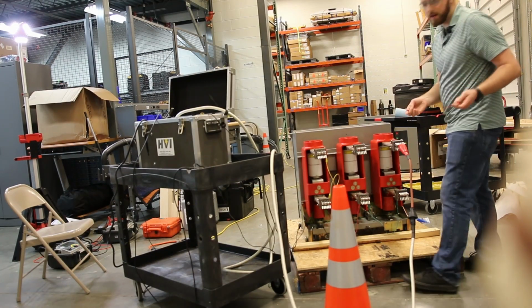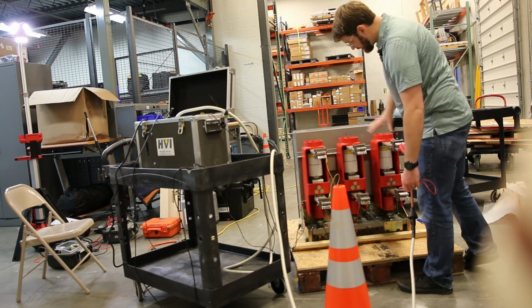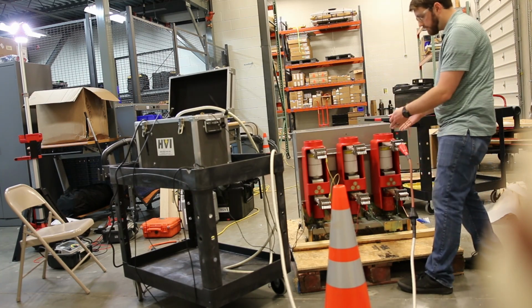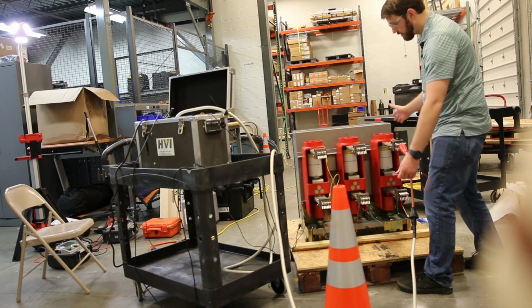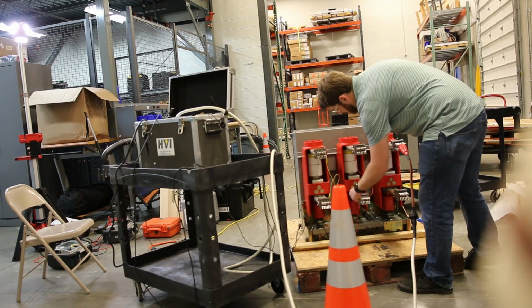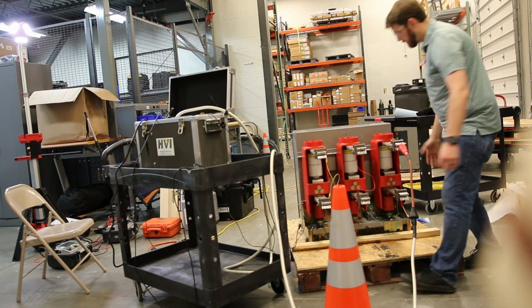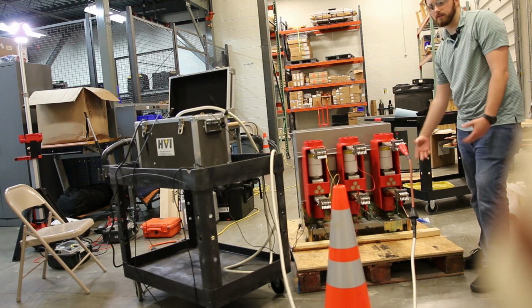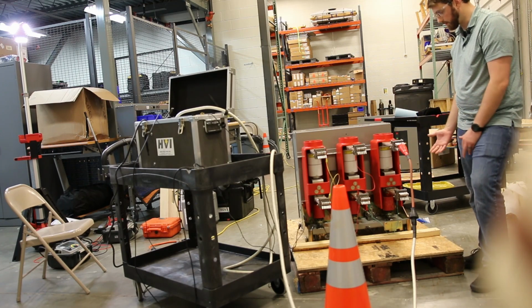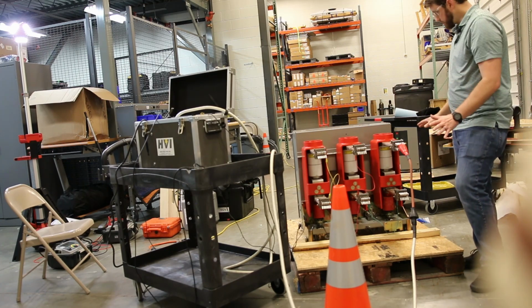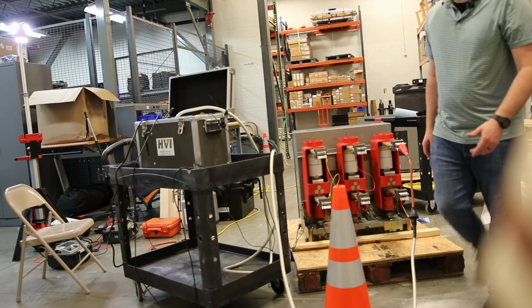Just to reiterate what we're doing, the line side of C phase to everything else, and that verifies, well, number one, it verifies the vacuum bottle integrity. That's the primary thing that we're doing, right? But we're also checking that it's open to everything else.